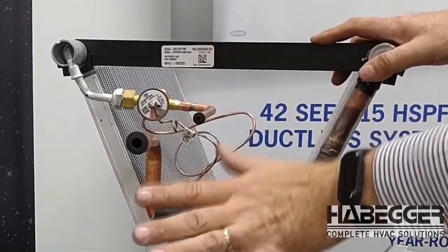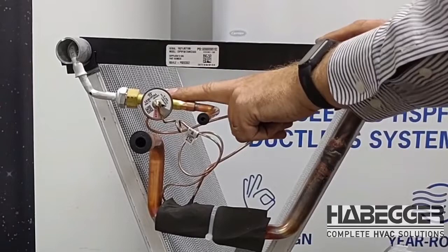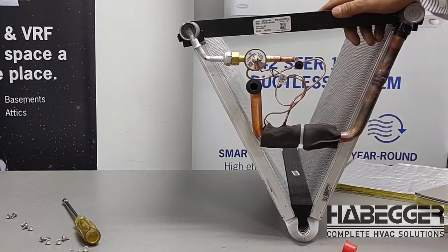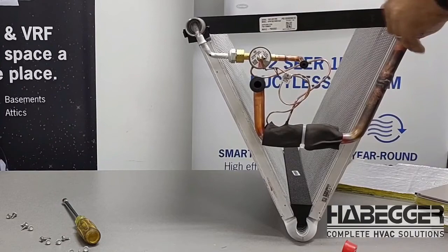For installation practices when it comes to brazing, we've got our nitrogen running through it — standard practices. But this becomes critical: we've got a shorter piece here on a horizontal plane, so this must be wrapped with a wet rag to contain the heat. When this TXV hits 212 degrees, it starts to cook. If it's too hot to touch for more than a second, you probably have something that is going to cause an issue down the road. Suction line dips down — definitely isolate this with a wet rag. No need to add or subtract refrigerant. This fits with all current specs: if a condenser at 15 feet takes 9 pounds of refrigerant, it is 9 pounds — no addition, no subtraction. Charge to sub-cool within 3 degrees — standard, factory spec.